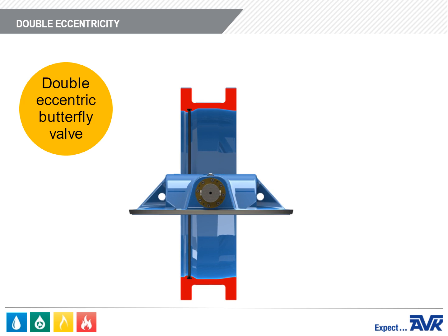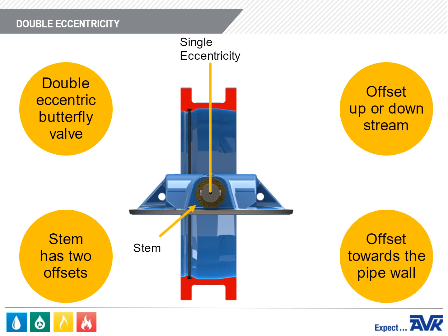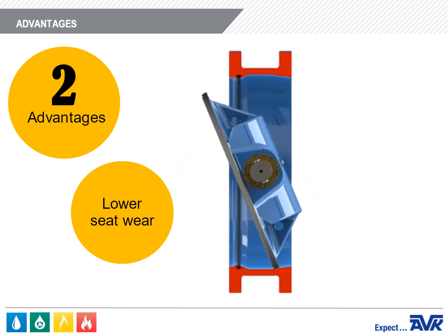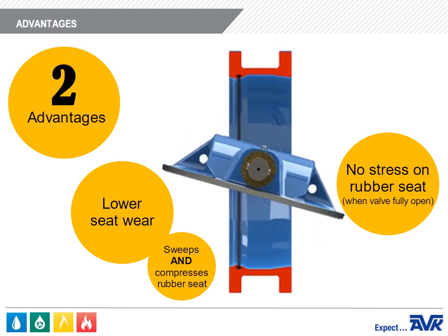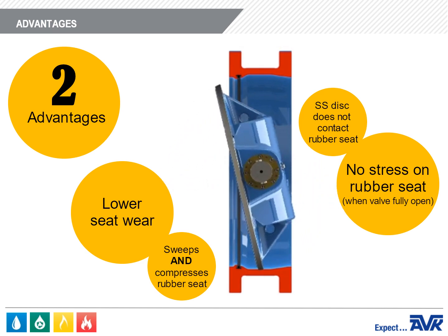The Series 766 is a double eccentric design butterfly valve, meaning the stem has two offsets. There is an offset which is up or downstream, as there would be for a single eccentric butterfly valve, and there is a slight offset towards the pipe sidewall. There are two advantages to the double eccentric design. First, lower seat wear — due to the camming action, the stainless steel disc doesn't just sweep the rubber seat when it closes, it also compresses it. Second, when the valve is fully open, there is no stress on the rubber seat, because no part of the stainless steel disc contacts the rubber seat when fully open.